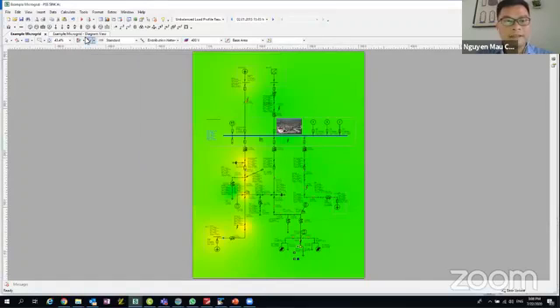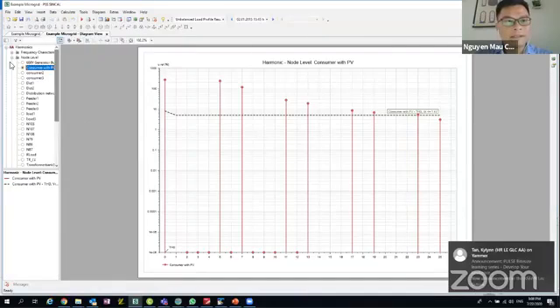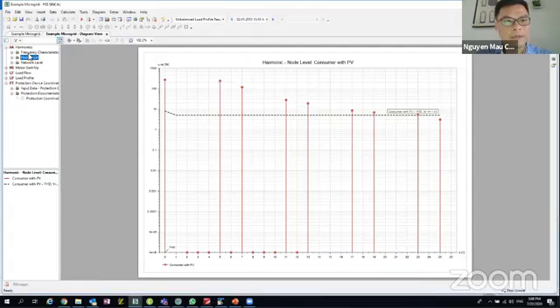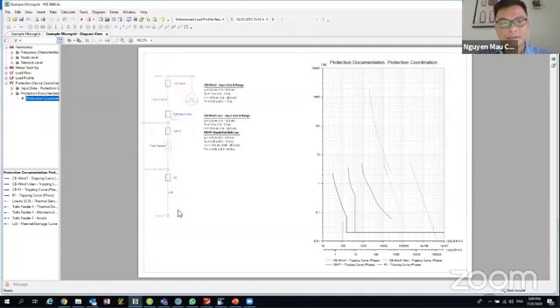And the other thing is you can calculate the harmonics. You can calculate the THD here at each node, and you can see here the dashed line is the requirement, and here you can see the harmonic at this node is very high. We need to have, let's say, the harmonic filter, and moreover you can have the protection coordination. So you have a certain number of elements here, and this is the protection coordination. There are many other studies we need for a microgrid.